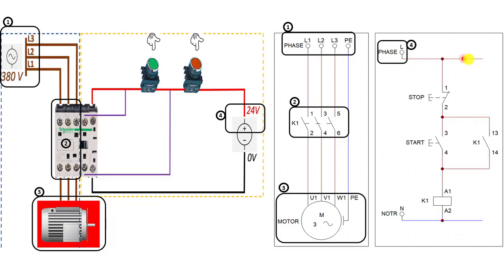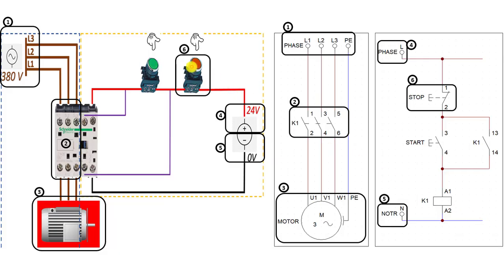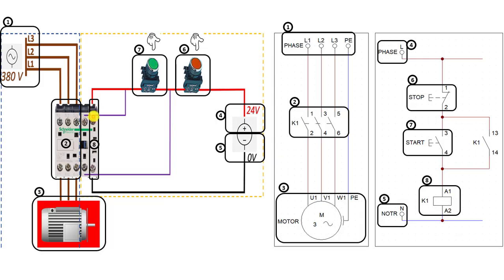For the control circuit: the 24-volt signal phase is shown in the circuit diagram, and the neutral connection is drawn at the bottom. The stop button is a normally closed contact, so it is shown as a closed contact in the circuit symbol. The start button is a normally open contact, shown accordingly. The coil terminals A1 and A2 are shown in the circuit diagram. The normally open auxiliary contact, connected in parallel with the start button for sealing, is also shown connected in parallel.